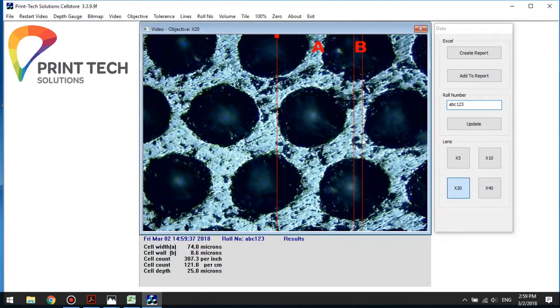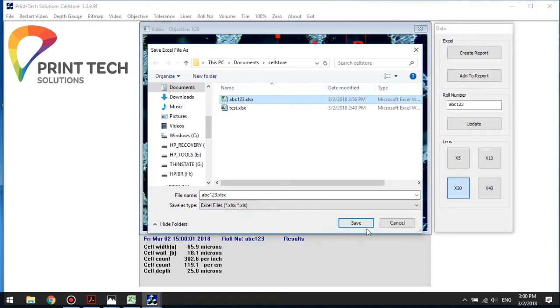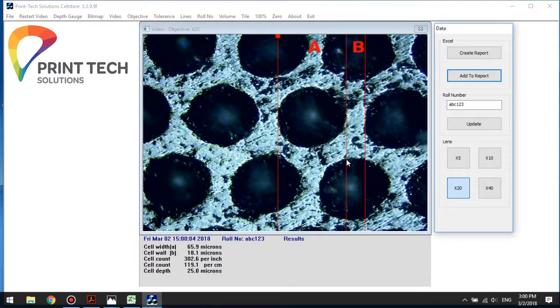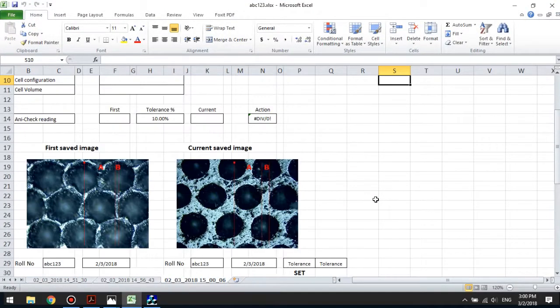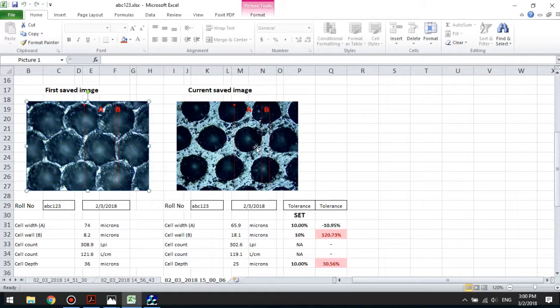Now I'm going to measure the wall again, taking an average through the wall using the B cursors, and also the cell opening. I'm going to save that data to my existing report by choosing add to report, entering the roll number, and saving. Here we've got the original condition of the anilox at the point of our first measurement — whether that be a new cylinder or one currently in the press — and now we've taken a measurement after a period of time looking for wear. You can see clearly the difference between a fresh anilox cell and a worn cell.